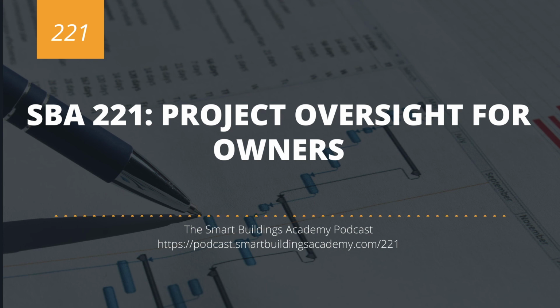CX being commissioning. Then you're going to do doc reviews, as I mentioned. You're going to review your red lines. You're going to review your O&Ms. Highly recommend you get an online as well as a physical version of your O&Ms. And then you're going to do your training closeout. Ideally, your training requirements would be dictated in the standards and included in the specification, and you would have a clear expectation of training deliverables. That being said, in some cases, that does not happen, and this is your last opportunity to ensure that your operational team is able and capable to execute whatever task they need to do utilizing the building systems that were put in place.